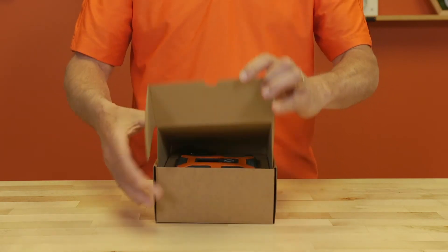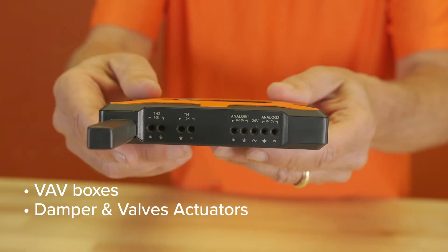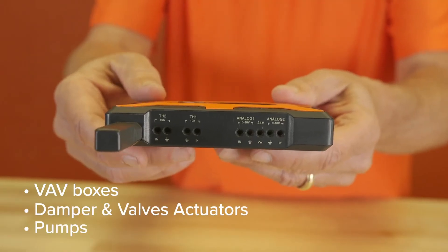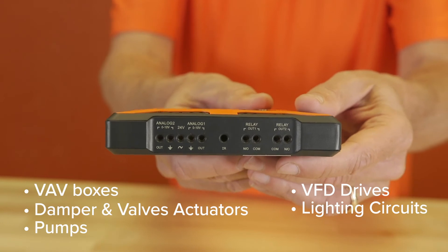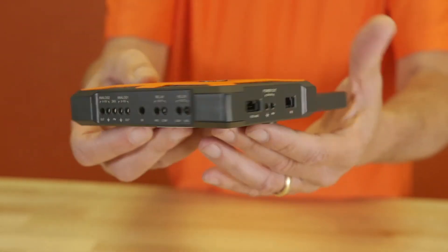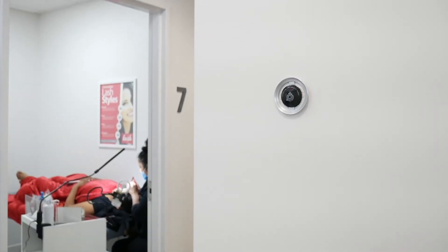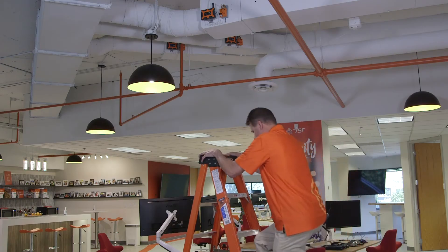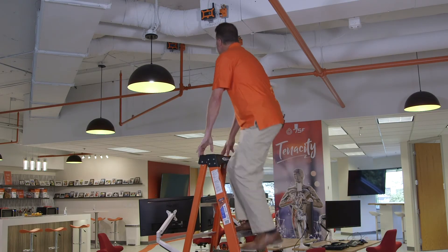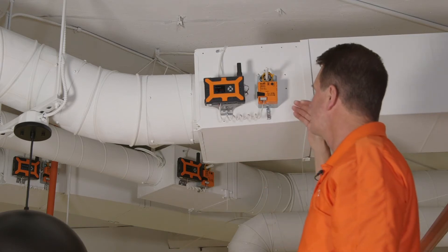The SmartNode is for everything else in the building such as plant controls and terminal units. Think of VAV boxes, damper and valve actuators, pumps via VFD drives, and lighting circuits. Sensors of all kinds are monitored by a SmartNode and used as inputs for all types of sequences. Here we have a wall sensor with temperature and humidity for zone control. A SmartNode has the inputs and outputs needed to control a VAV box and any other kind of zone control system.